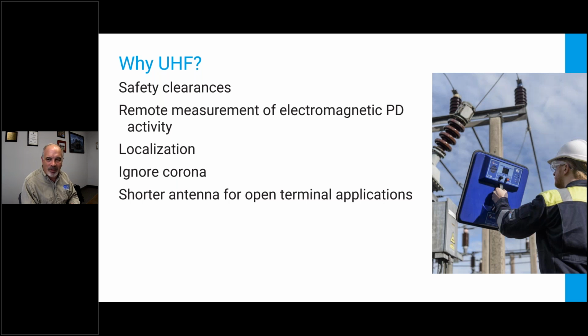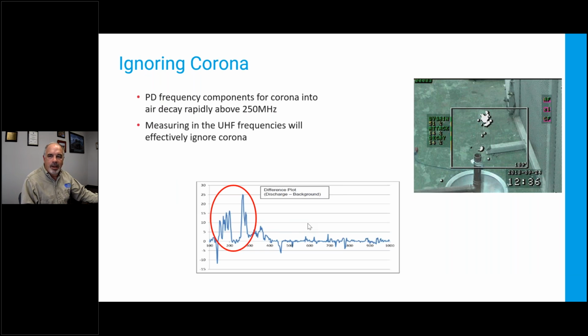What's nice is I can walk around the substation at a standoff distance and find stuff in exposed air insulated switchgear pretty easily. Ours in particular is designed to ignore corona, so the instrument rolls off below around 250 megahertz. We avoid seeing corona discharge because that's not destructive, so we want to ignore it as best we can.